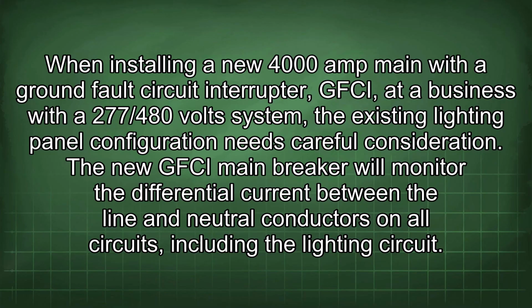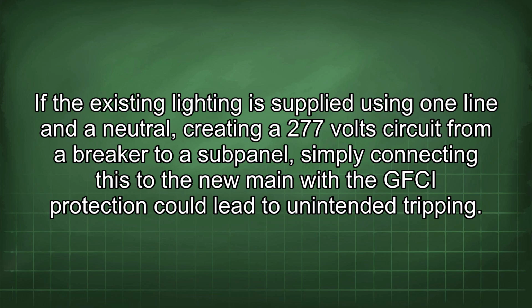When installing a new 4000 amp main with a ground fault circuit interrupter, GFCI, at a business with a 277/480 volt system, the existing lighting panel configuration needs careful consideration. The new GFCI main breaker will monitor the differential current between the line and neutral conductors on all circuits, including the lighting circuit.